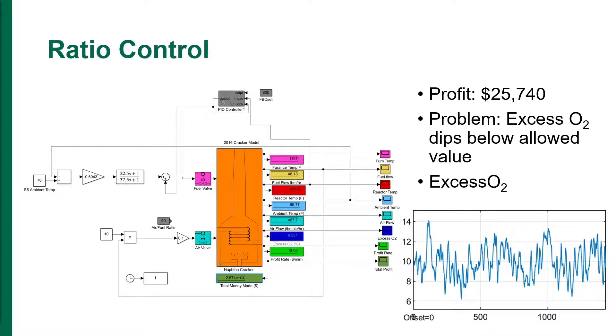In order to control the excess O2 at the set point, a ratio controller between the fuel flow and the air flow was implemented. The ratio of the air flow to the fuel flow is 10. The resulting profit was $25,740.